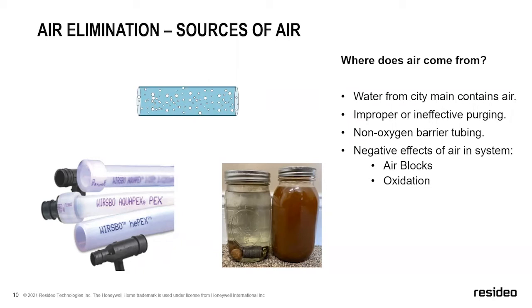This is an example they've had at some of the plumbing counters I've gone to, where they fill two jugs with basically a mixture that prevents that oxygen attack. And you see common systems. You've got black iron fittings in there, copper fittings. I think there's some brass. That's commonly seen in a hydronic system. And then on the right is what happens if you don't take care of that oxygen. So I'm going to talk about our air eliminators that help get rid of the air bubbles.